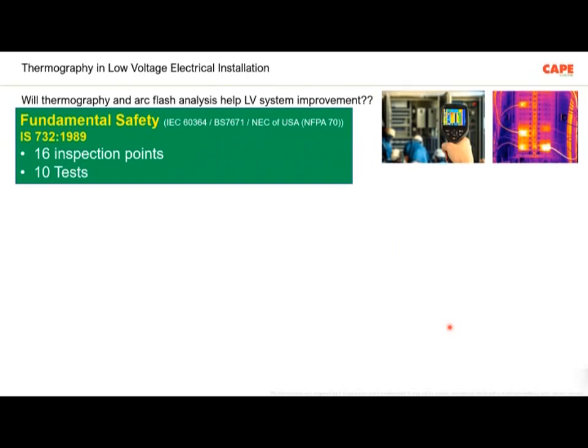Let us analyze whether thermography and arc flash analysis help low voltage system improvement. We are talking about low voltage, not about the other voltages. Please understand. In low voltage engineering, there are fundamental safety requirements. That means the basic safety requirements. It is included in the IEC 60364. That is the IEC standard. In the British standard, the same is BS 7671, or NEC of America, NFPA 70, or IS 732 for us, the code of practice of wiring.